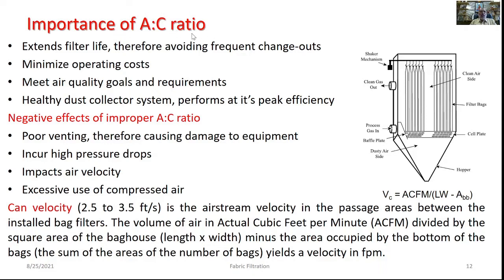The A:C ratio needs to be maintained at the correct level. It extends filter life and therefore avoids frequent changeouts of the bags. It also minimizes operating costs; if the air-to-cloth ratio is too high or too low, it may cause reduction in efficiency, overload, and deflection of bags with undue pressures, increasing maintenance needs.